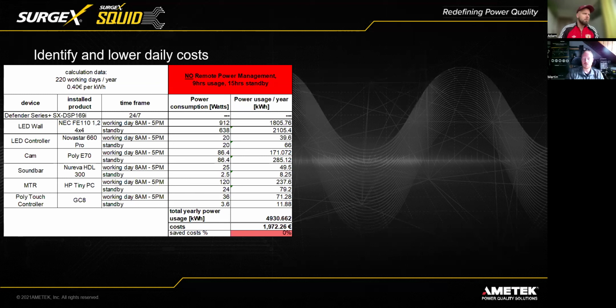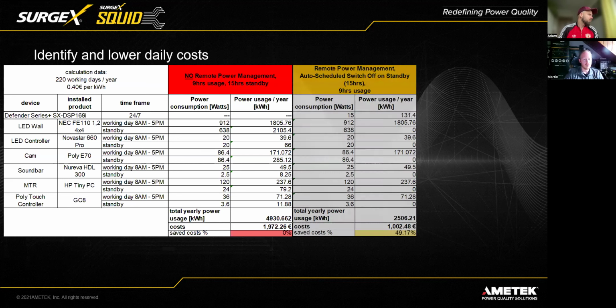Nobody's working in a conference room on weekends or at night, so we defined a working day from 8 a.m. to 5 p.m. and installed one of our PDUs to schedule the usage, cutting away the standby timing. We programmed triggers so the installation starts at 8 in the morning and switches off at 5 in the afternoon. As you can see, we're almost saving 50% already.